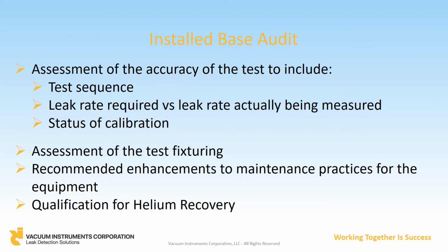VIC offers a complimentary installed base audit to all customers as well as potential customers who have a sizable installed base of leak detection equipment. This audit can encompass custom leak detection equipment as well as leak detectors themselves. We offer to audit not only your own equipment in your installed base, but all the leak detection equipment that you currently own. During the audit, we will also evaluate feasibility and the return on investment if a helium recovery system were to be implemented.